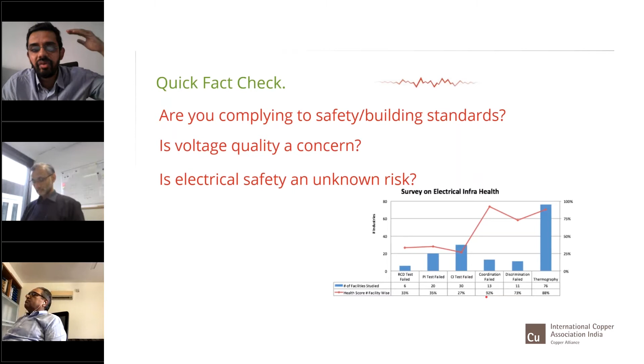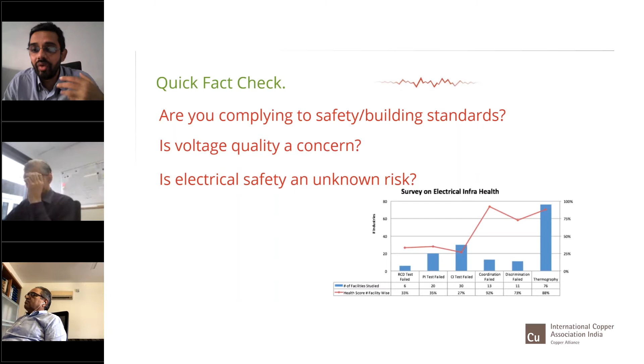RCDs, almost 33% of them failed the simple test of conforming to an OEM's time current coordination curve. This means that in the event of a crucial fault in the system, the last mile protection you have in terms of your RCD is not going to act. It is not going to protect your installation. So how much more vulnerable can we be?